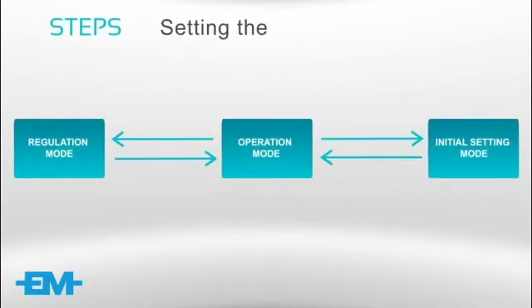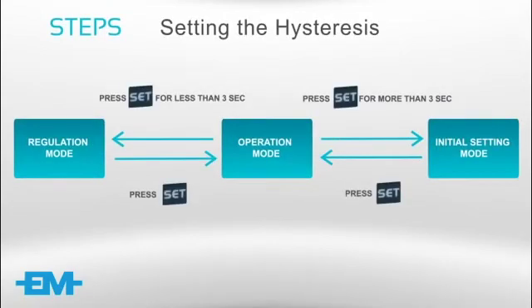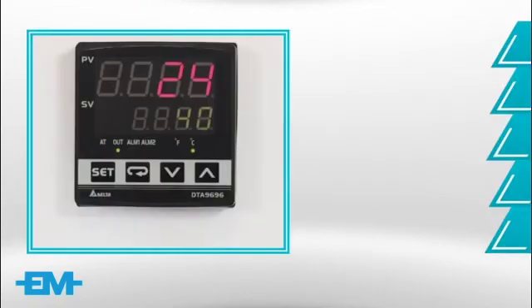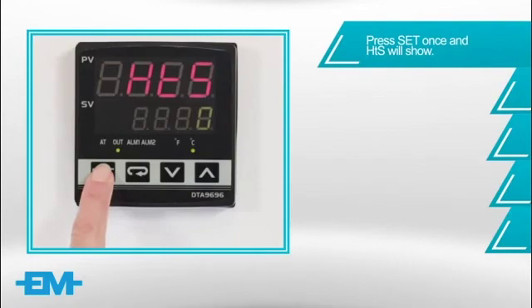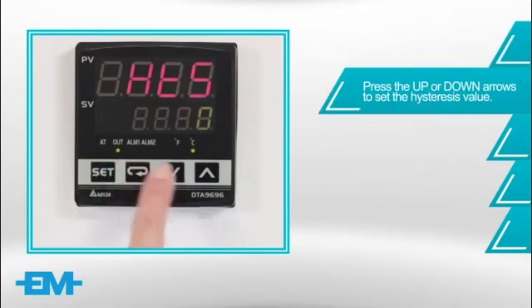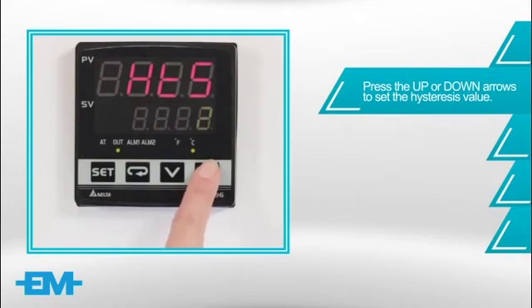The hysteresis is set in regulation mode. To set the heating hysteresis, press set once to enter the regulation mode and HTS will show. Press the up or down arrows to set the desired hysteresis.